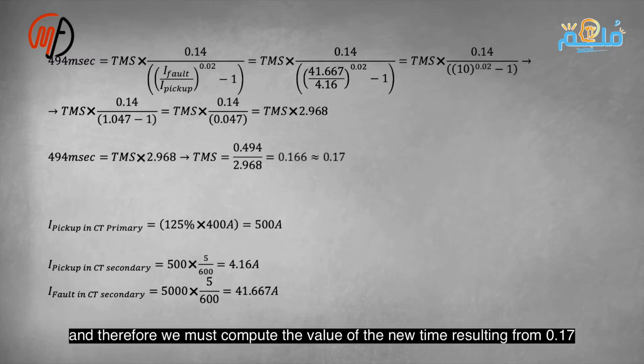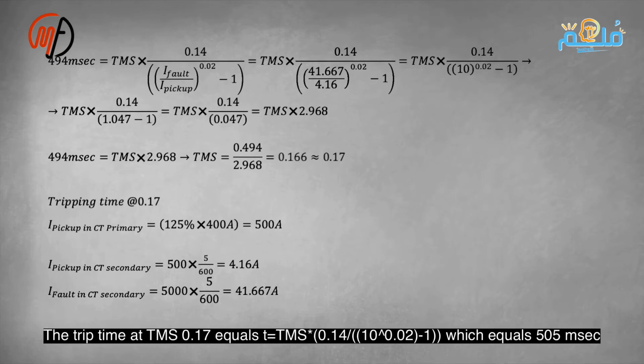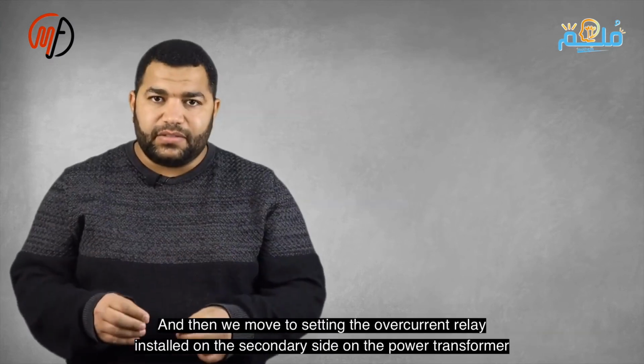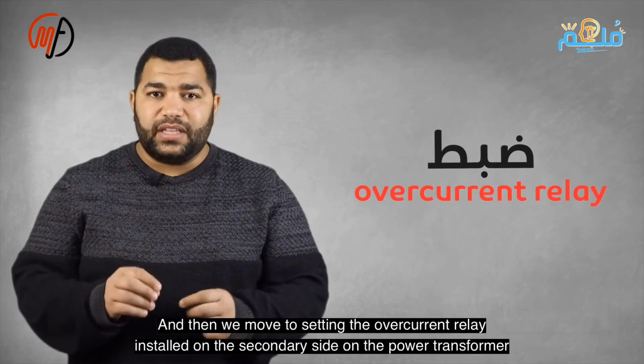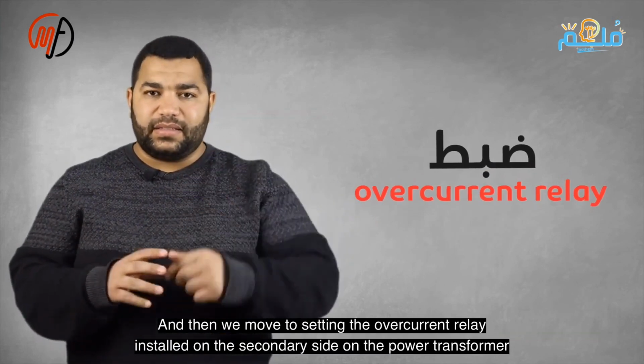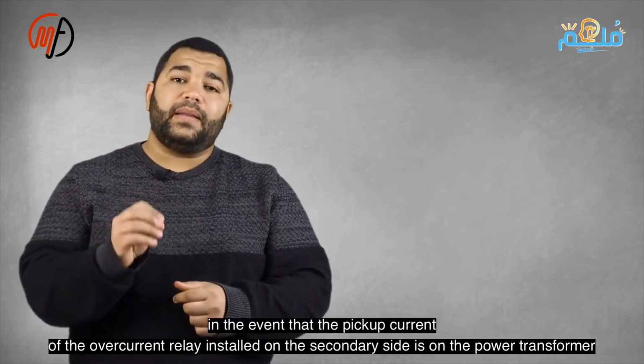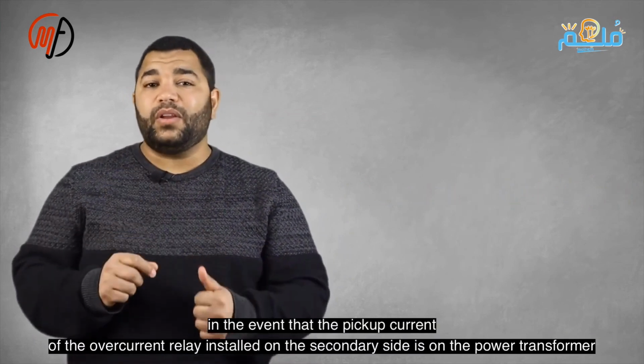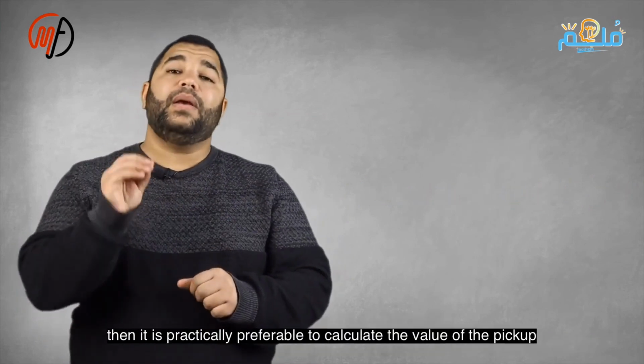When setting the pickup current, it's better to calculate from the rated current rather than the maximum load current. Both are correct, but the rated current is commonly used in power stations. Set the secondary side overcurrent relay. For pickup current setting, calculate pickup from rated current, not maximum load current. Both are correct, but this is common in power stations.